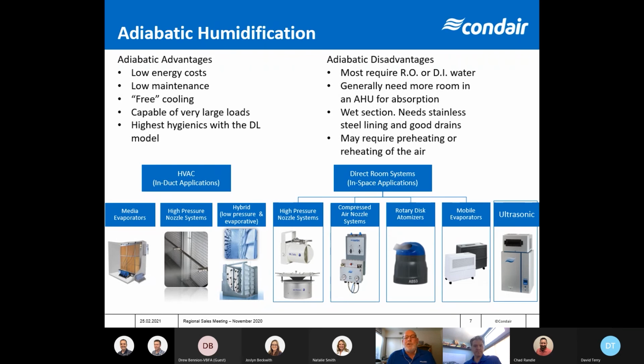Some of the advantages and disadvantages: obviously the big advantage with the adiabatic systems is very low energy costs. Low maintenance, in that by far most all of these will use RO or DI water, so of course the maintenance falls onto the RO or DI treatment system. The free cooling that we talked about, capable of big loads, and the hygienics. Some of the disadvantages, if we want to call it that: most of these do require RO or DI water.